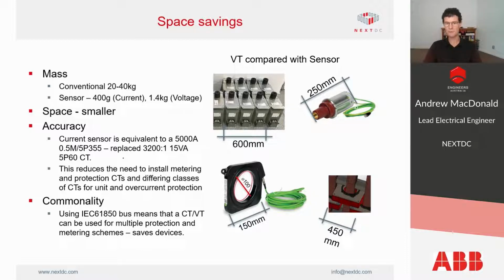Because they are also useful as metering devices, it allowed us to not put metering CTs in all the locations where we potentially would have in the past. The other advantage is that using the 61850 bus meant that the CT and VT, the current and voltage signals, can be used in multiple protection and metering schemes across multiple devices and shared over the bus, which reduced the number of current and voltage sensing devices that we needed to install.